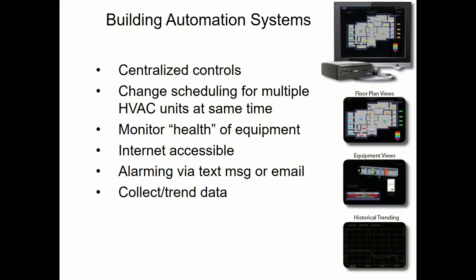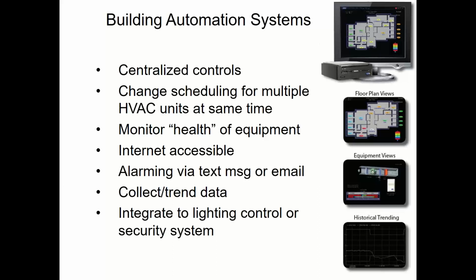Somebody says, oh, every Tuesday morning my system does this weird thing and it gets super hot in here and I don't understand why. Something's broken. I can go look at the trend data and be like, well, every Tuesday morning your set point gets jacked up to 90 degrees for heating for an hour. That's why it's so hot in here. Well, why the hell is that? I don't know. I don't know why you programmed that in, but let me undo it for you. All right, it's pretty easy to go look at some of that stuff then if you have the trend data.